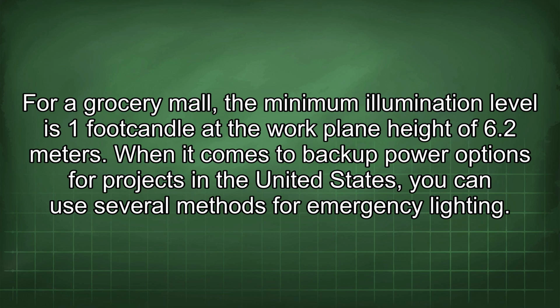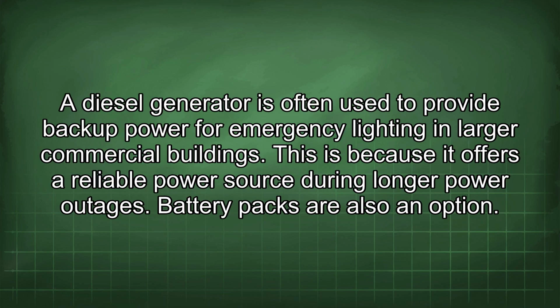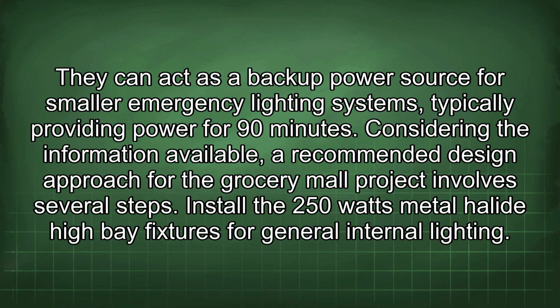A diesel generator is often used to provide backup power for emergency lighting in larger commercial buildings. This is because it offers a reliable power source during longer power outages. Battery packs are also an option. They can act as a backup power source for smaller emergency lighting systems, typically providing power for 90 minutes.